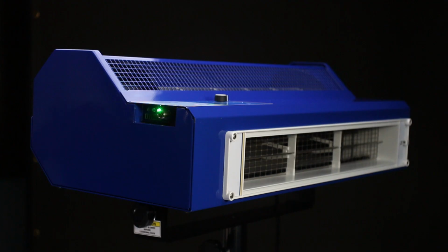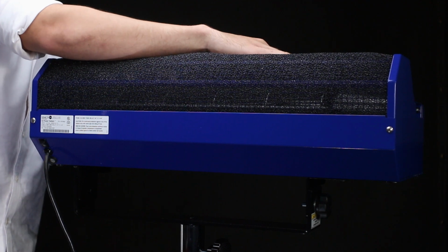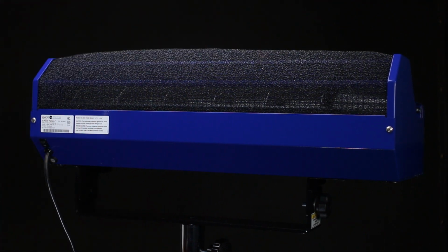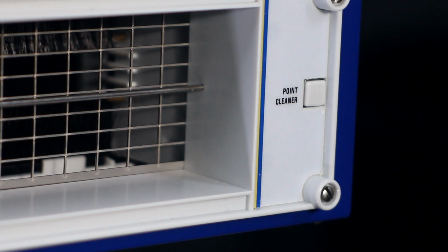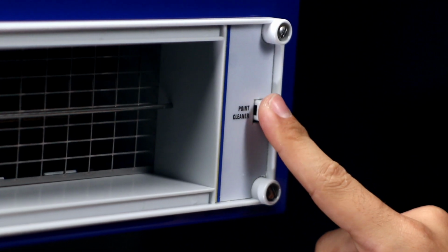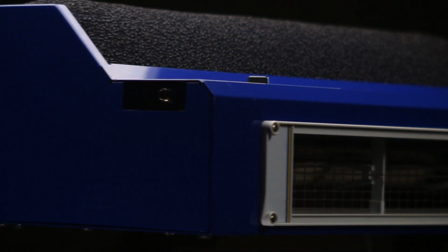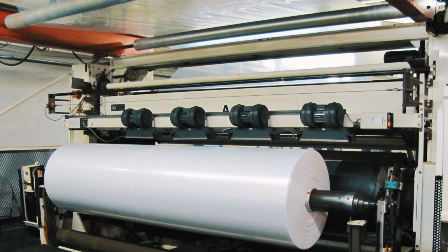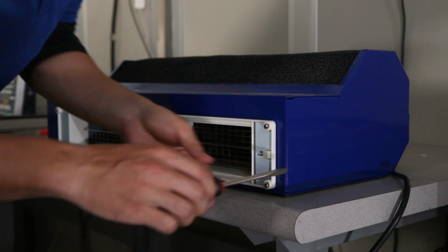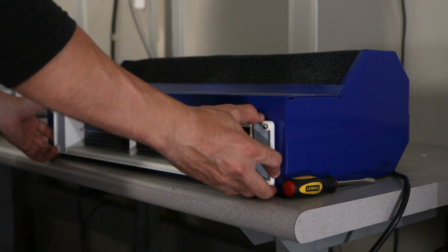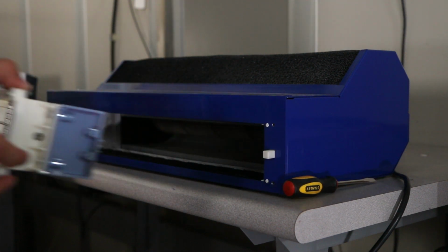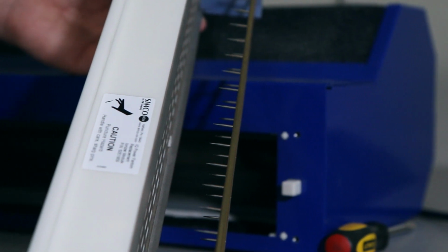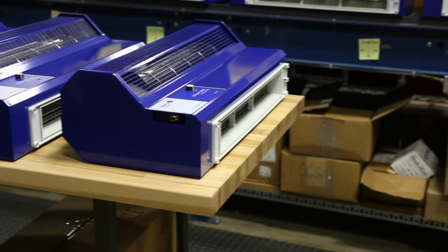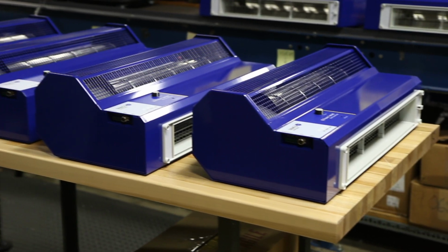Automated cleaning and a replaceable 10 PPI filter keep the Fantom clean. It is also extremely easy to maintain. The self-cleaning system automatically initiates when powered on and can be manually triggered as well. While the Fantom is extremely durable, harsh industrial environments can take a toll on even the most rugged equipment. For this reason, the ionizer duct assembly is replaceable, which means with regular maintenance, the Fantom will meet your static neutralizing needs for a long time.